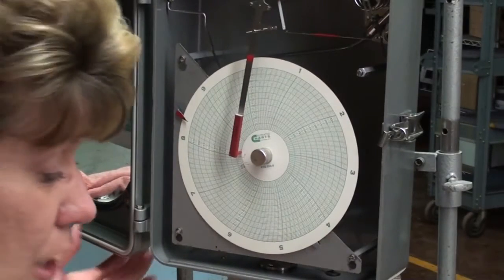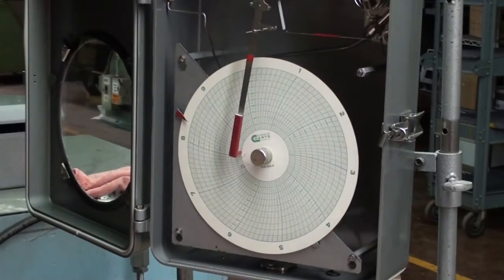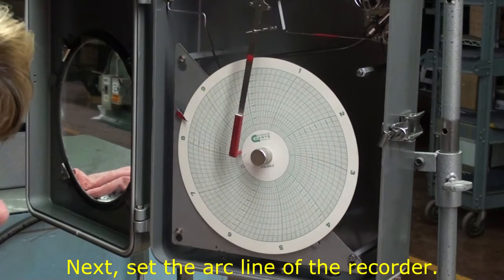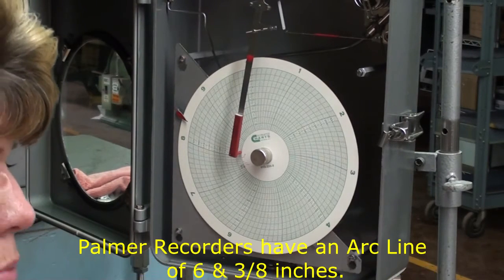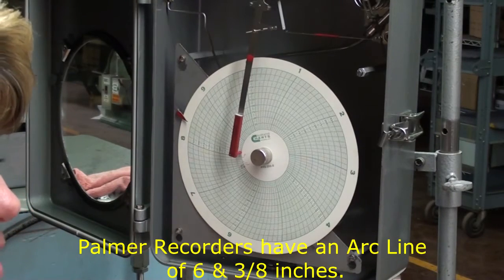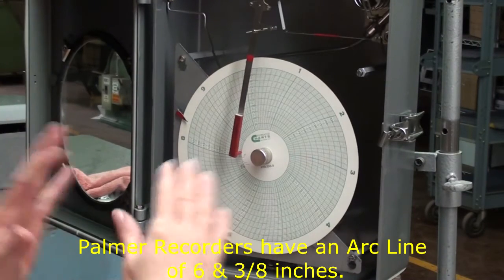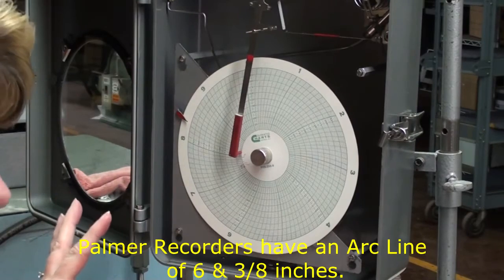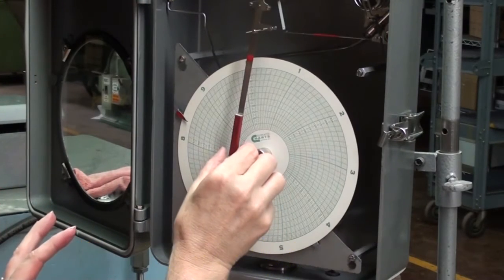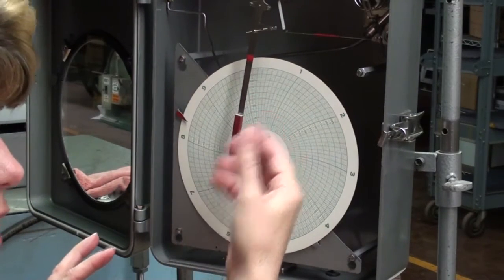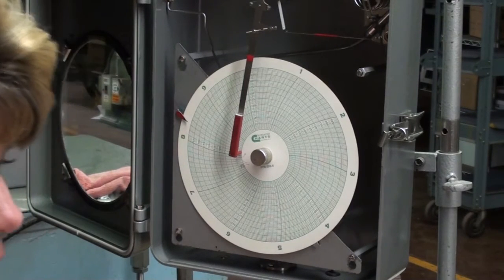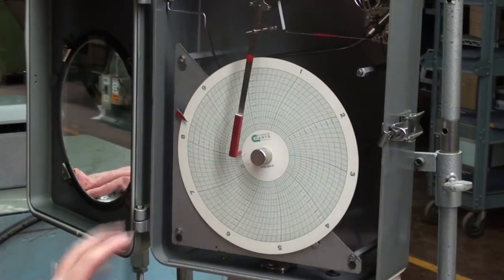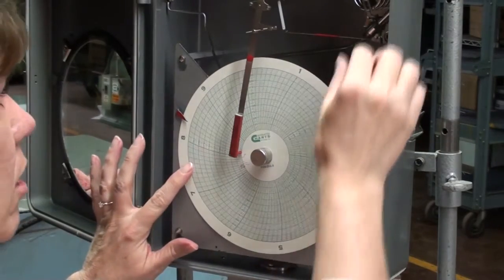After you get the pin tension set, then you can work on the arc line of the recorder. And the reason that an arc line is so important is it is a point of calibration that is always the same. If you just calibrate this recorder like it is right now, any time you remove this pin and put it back on, your calibration is going to change if you do not put it back on the arc line. The arc line is a measured distance. So let's check our arc line.